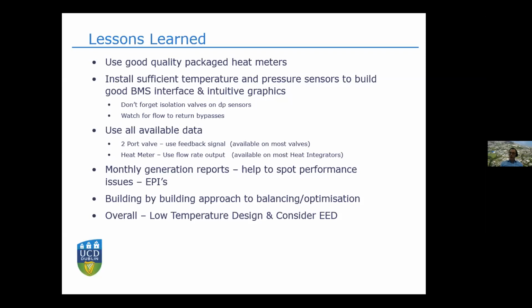For large commercial buildings, put in DP sensors at all the heat exchangers, with temperature, flow and return temperatures on primary and secondary sides. When you put in those temperature and pressure sensors, have isolation valves, because you don't want one to fail and then have to wait till the end of the heating season to fix it. So allow for things like that in the initial design, and watch for flow-to-return bypasses.